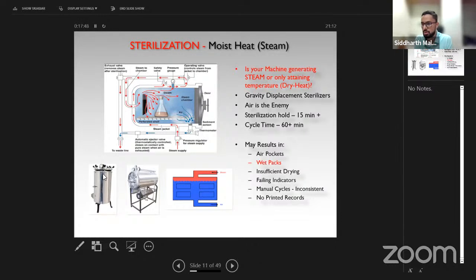They come pre-sterilized only. Sterilizing it later could be a difficult proposition because autoclave moist heat is going to interfere with the ink. So that is why it is never autoclaved. Either it is gamma radiated or it is ETO sterilized. Our suggestion is to use a single use one, sir.